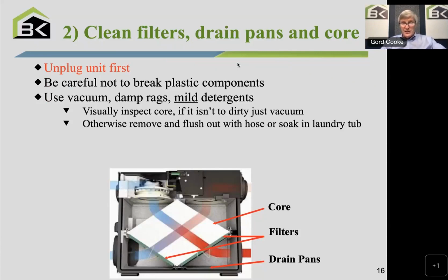So that's the core itself, and they typically slide out and they get a little sticky. It might take a little bit of persuasion just to get your hands in, but be careful not to delaminate the core. Have hands on it, not fingers grappling at it, and pull thoroughly. Sometimes you need a little silicone spray when you go to put it back in to make sure the tracks are lining up. These weigh in typically no more than 15 or 20 pounds. They're not that heavy, and they're pretty rugged unless you're dropping them. Some are made out of aluminum, some are made out of plastics. If you drop them, they're going to get dented or damaged. So you just need to be a little careful around that. So that's the first thing to think about.